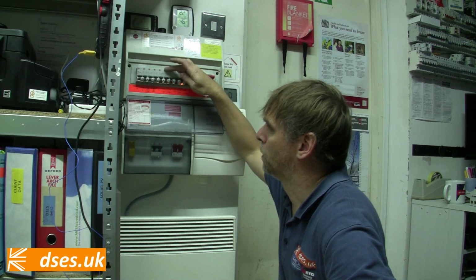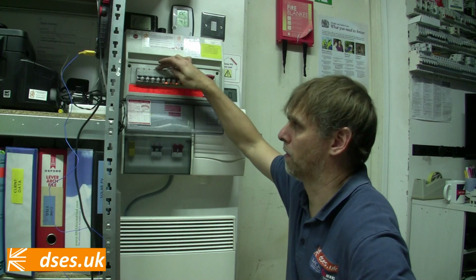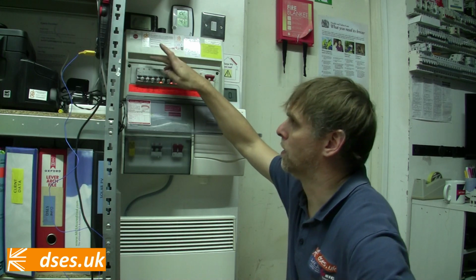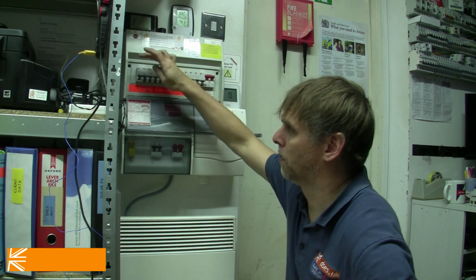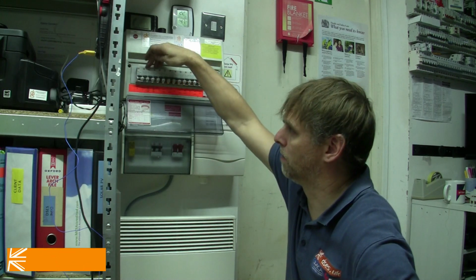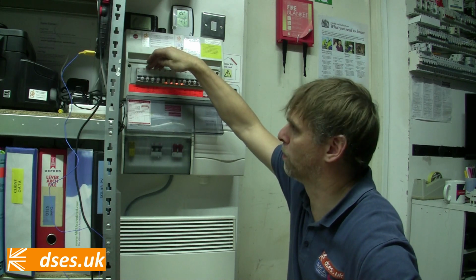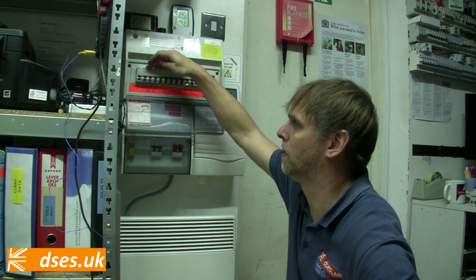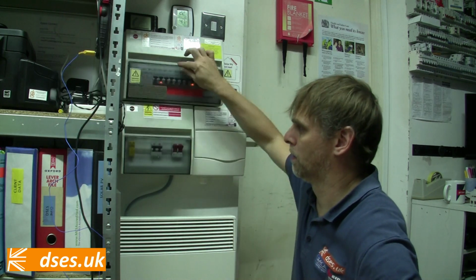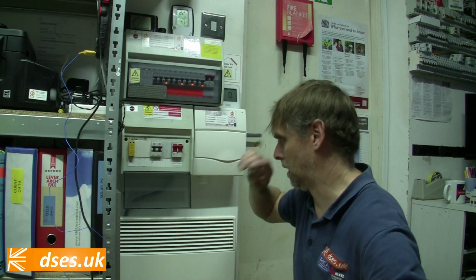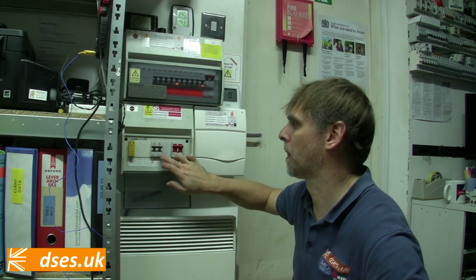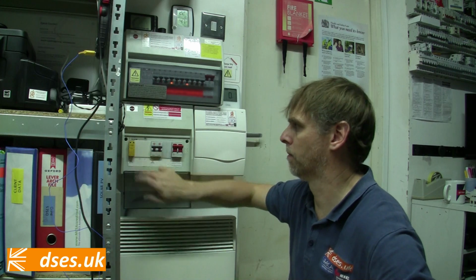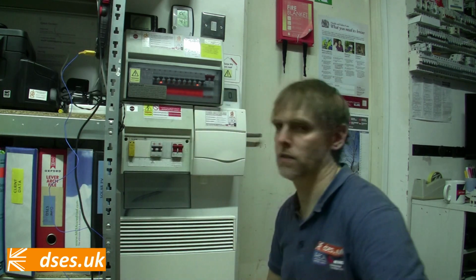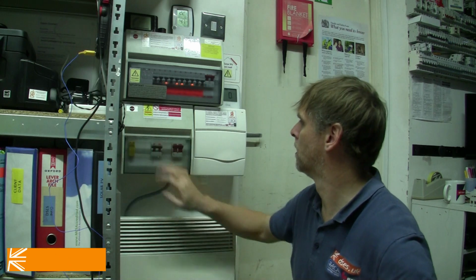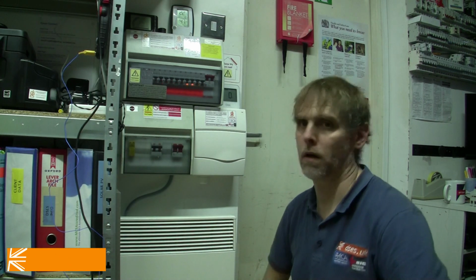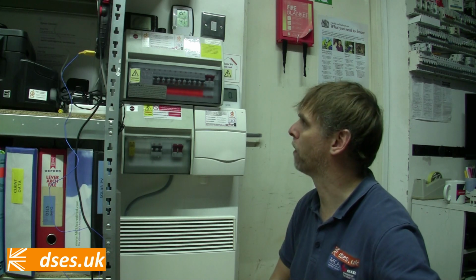What else we got here? Kitchen ring, oven, lights down and landing, the smoke and intruder alarms, lights up, and then the feed to DB2. Obviously these last three here, lighting and intruder alarms, as I said before, are just RCBOs, no point putting them on AFDDs, and this is an ordinary breaker feeding DB2, because as I said, I don't want my Twat Cave on an RCD, and this is just the surge protector breaker here. Surge protector is still showing good. Marvellous. So I'm going to leave that flashing away and we'll see how things go.